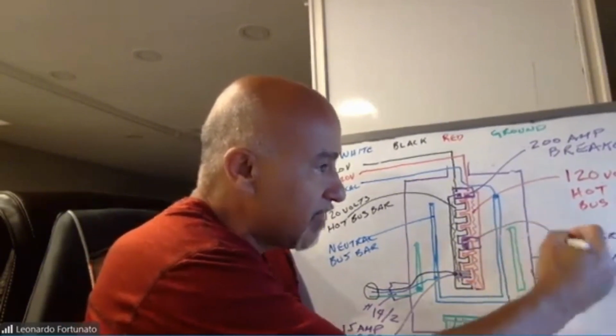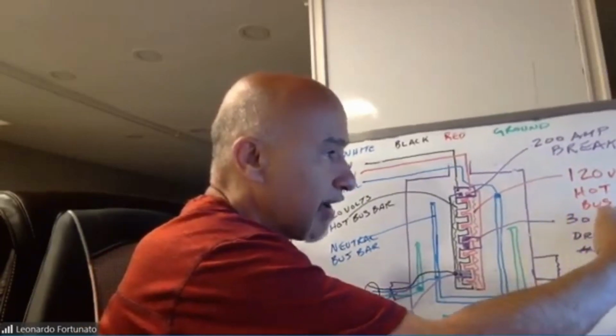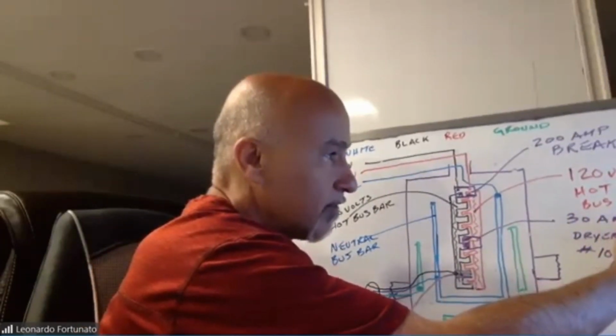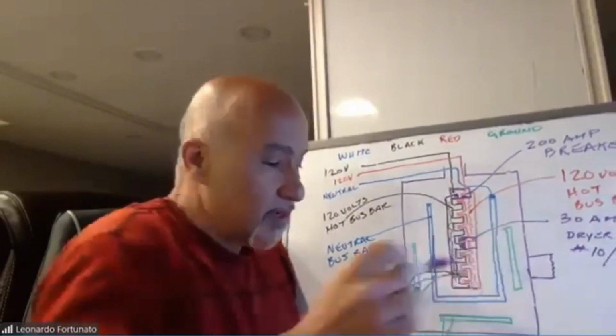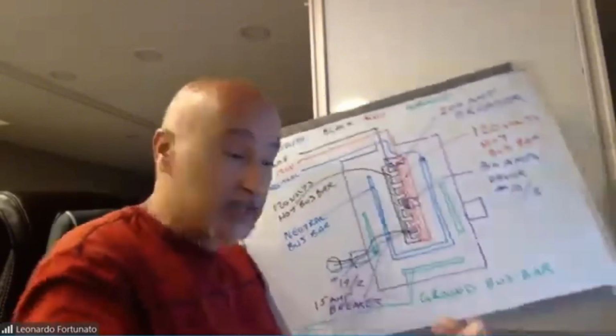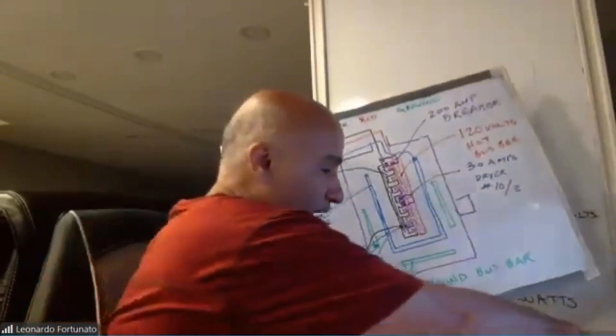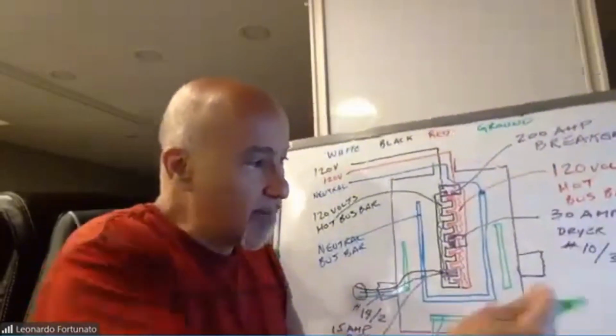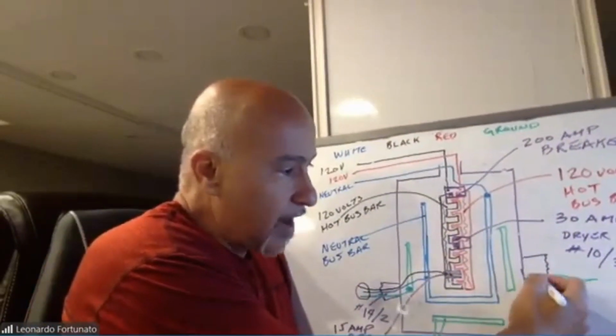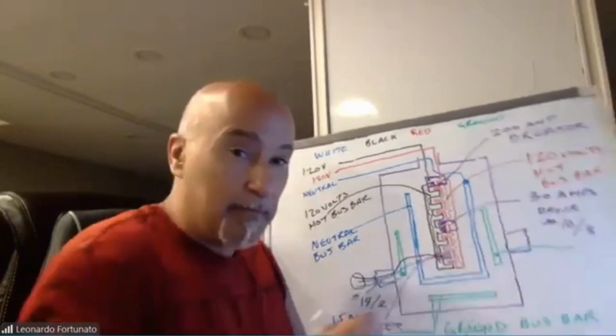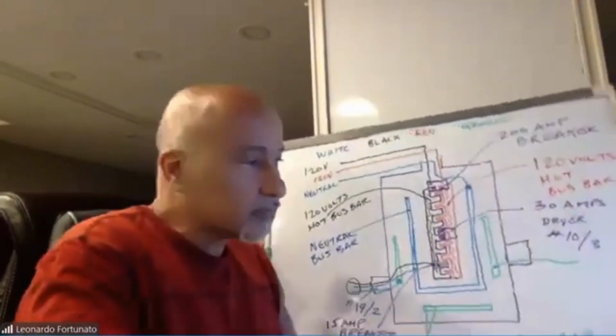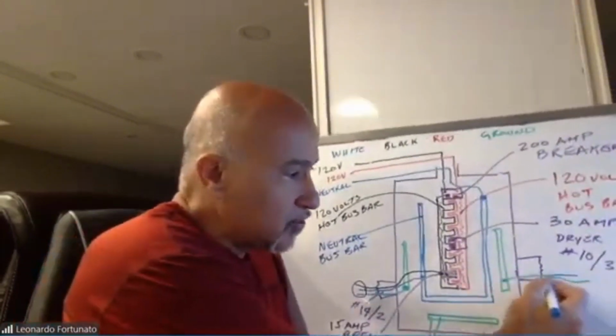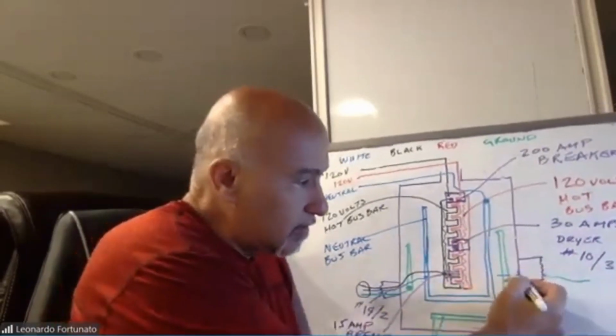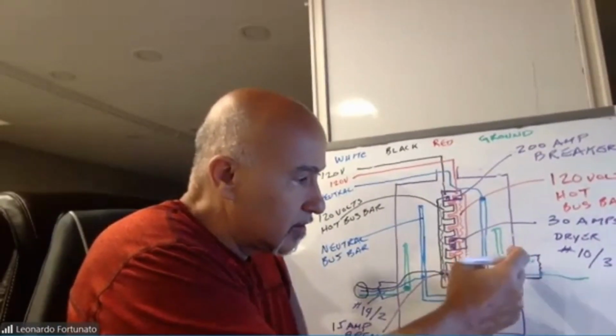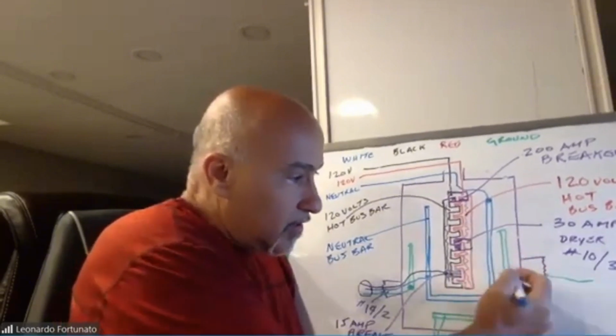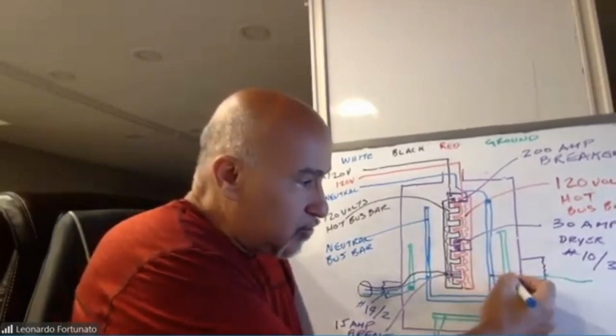I now need for this a 30 amp breaker. 30 amps. Let's connect the wires, ladies and gentlemen. Simply, we are going to start with the first wire, which is the easiest. We come in, ground wire. I'm going to connect it to the ground bus bar. Neutral. There's my ground. Here is the neutral. I'm going to connect it to the neutral bus bar.